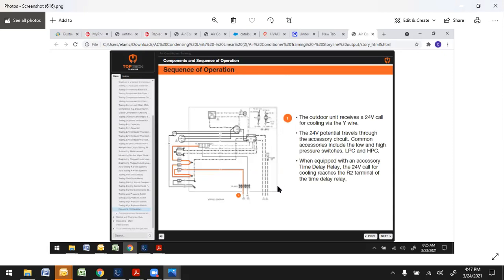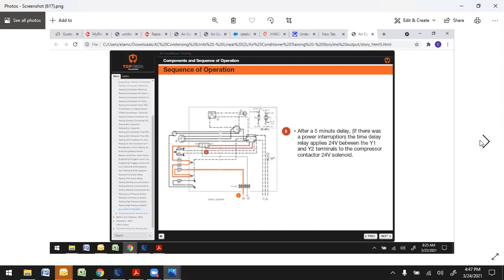So your basic sequence of operation for a normal single stage AC: the outdoor unit receives a 24-volt call via the thermostat wire. The 24-volt travels through any accessories that you may have included, low pressure, high pressure switches. If it's equipped with a time delay relay, it's going to stop in the time delay relay for whatever time frame that you have. A lot of them are 5 minutes.